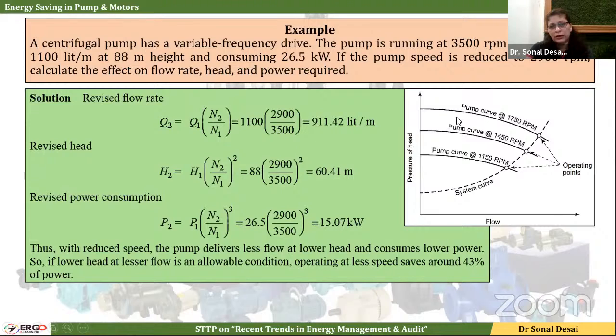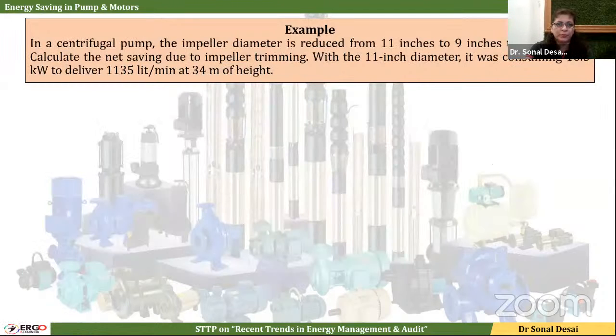So on a system curve and a head curve, the initial speed is shown. When it is higher, we are operating at this point. When we reduce it, it operates at this point, and with further reduction, we make it operate at a further lower point. So it will reduce head as well as flow, but at the same efficiency, we will have reduced power consumption. So this is one of the methods to reduce power consumption in the pump.